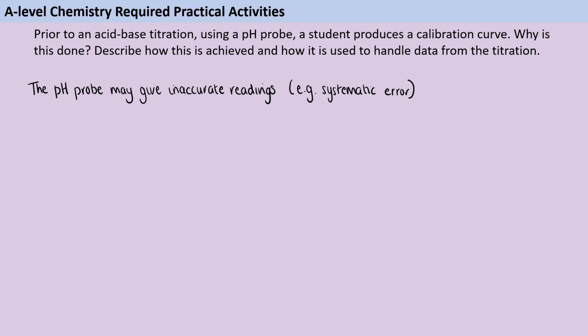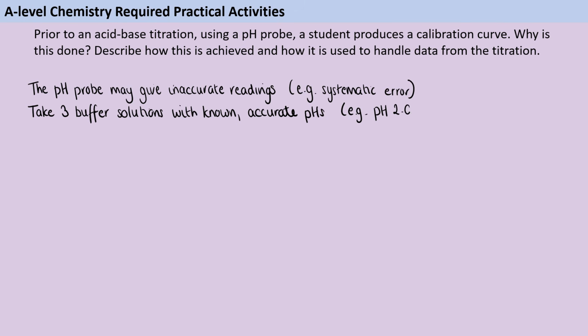So in order to do this, you're going to need a minimum of 3 pH buffer solutions. And those pH buffer solutions have known accurate pHs. You buy them and the company that sells them to you says, this is exactly pH 2.00. And we want to cover as much of the range of pHs as we can. So you might only have 4, 7 and 9 in school. Sometimes you can get ones that are a little bit broader than that, but basically you can only guarantee that your calibration curve is useful in the range of pHs that you've actually used to make it. So you want to be as broad as you possibly can.